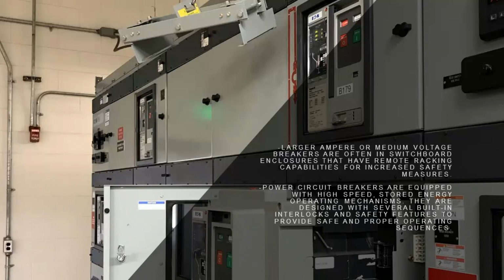So large ampere or medium voltage breakers are often in switchboard enclosures that have remote racking capabilities for increased safety measures. Got a little extra distance. It goes without saying. Power circuit breakers are equipped with high-speed stored energy operating mechanisms. They are designed with several built-in interlocks and safety features to provide safe and proper operation sequence. There's some of these breakers that you have to actually charge so that when it turns on, it's almost like a wind-up jack-in-the-box in a way. It's the best way to describe it.